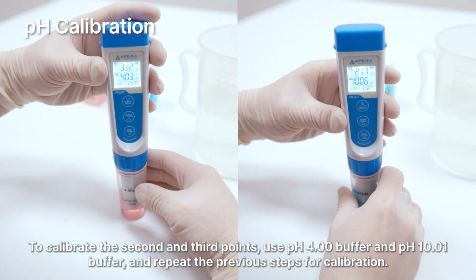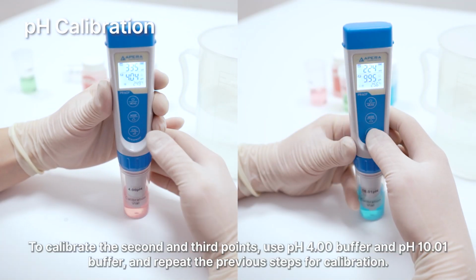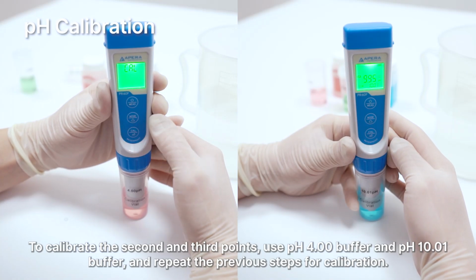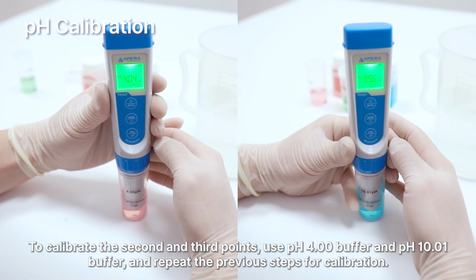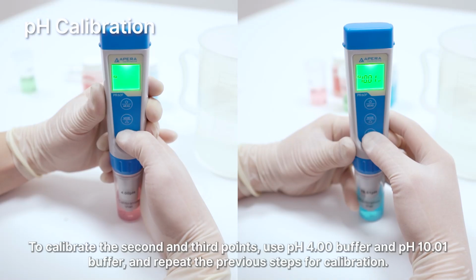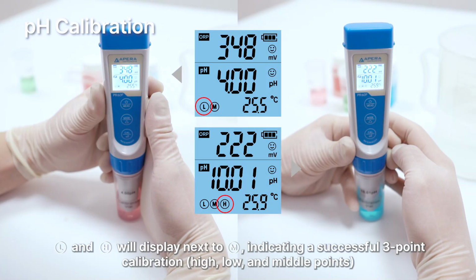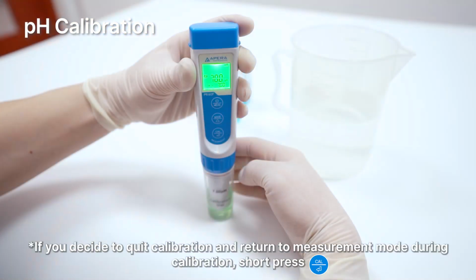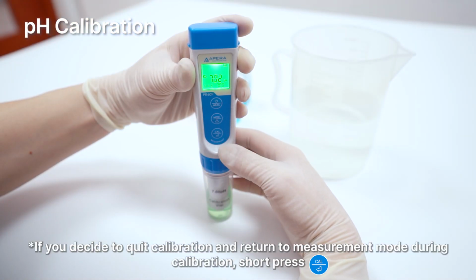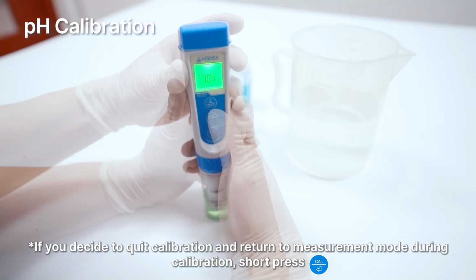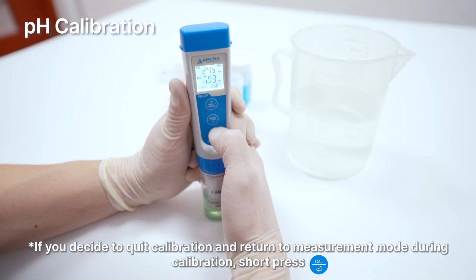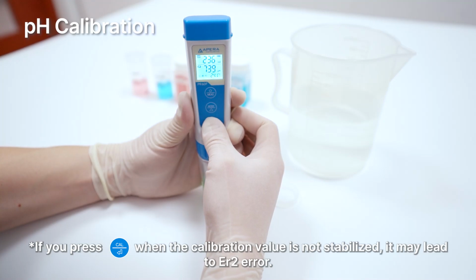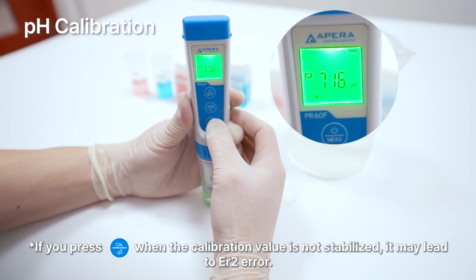To calibrate the second and third points, use pH 4.00 buffer and pH 10.01 buffer, and repeat the previous steps for calibration. Icon L and H will display next to M, indicating a successful 3-point calibration. If you decide to quit calibration and return to measurement mode during calibration, short press Cal button. If you press the confirm button when the calibration value is not stabilized, it may lead to Er2 error.